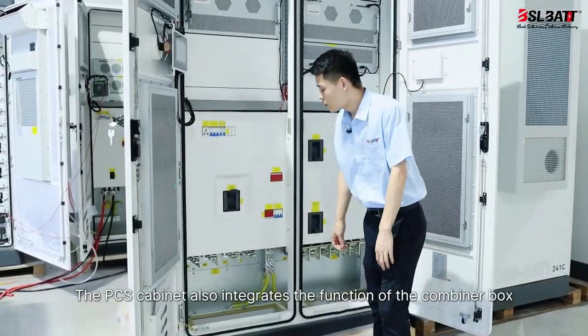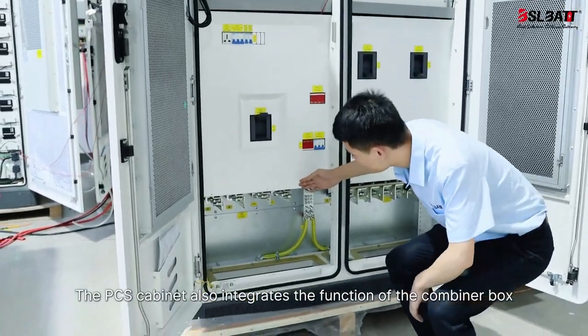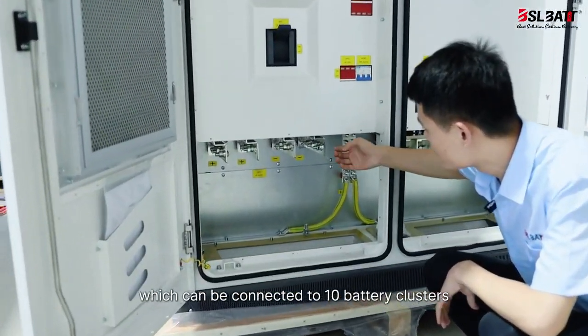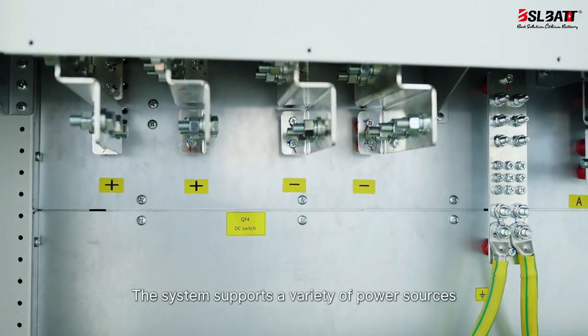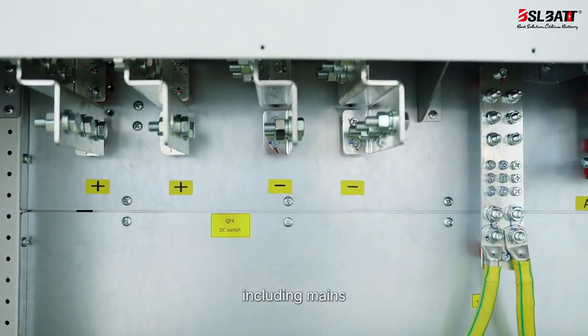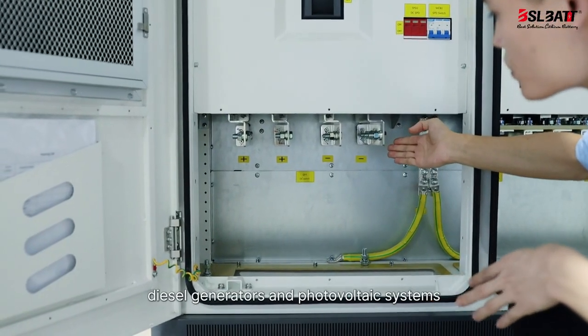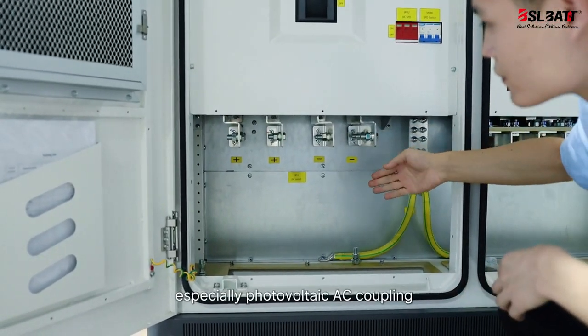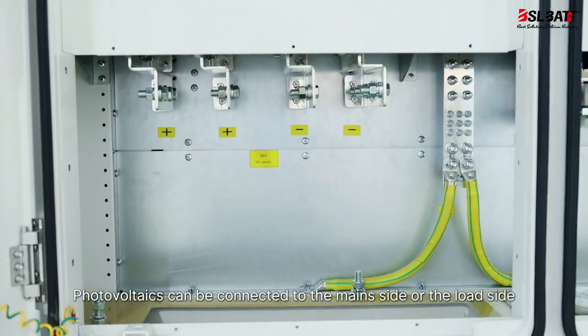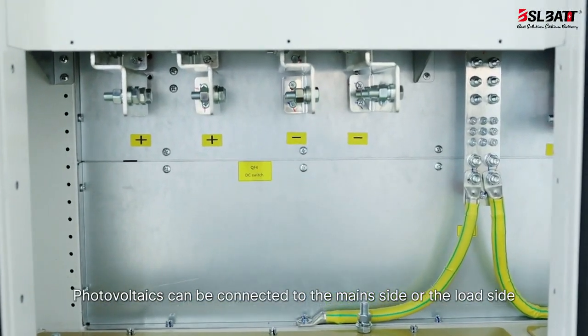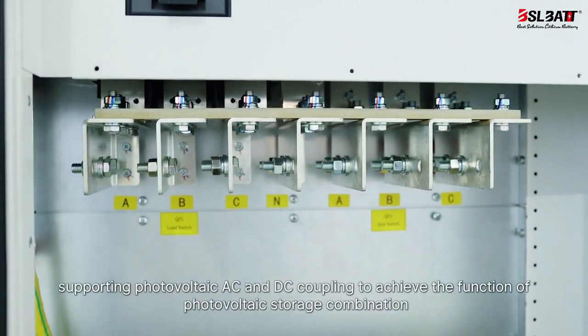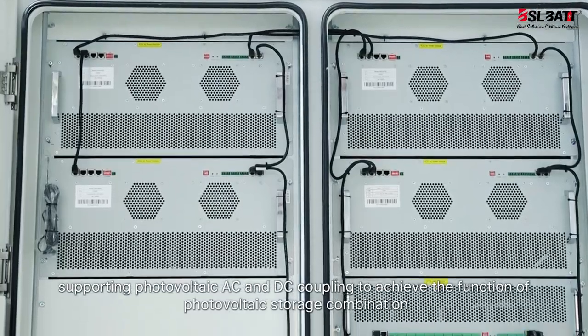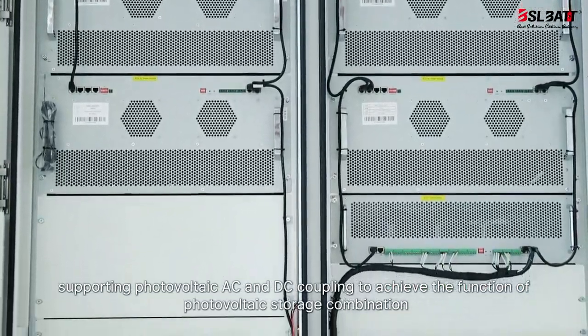The PCS cabinet also integrates the function of the combiner box, which can be connected to 10 battery clusters. The system supports a variety of power sources, including mains, diesel generators and photovoltaic systems, especially photovoltaic AC coupling. Photovoltaics can be connected to the mains side or the load side, supporting photovoltaic AC and DC coupling to achieve the function of photovoltaic storage combination.